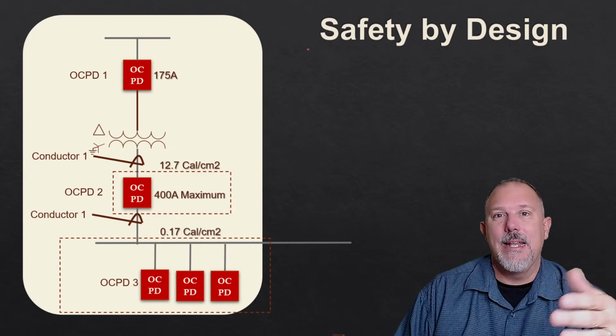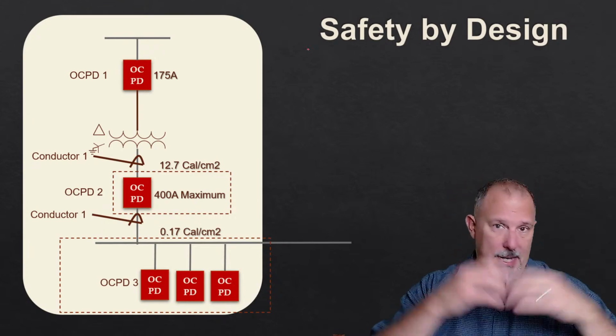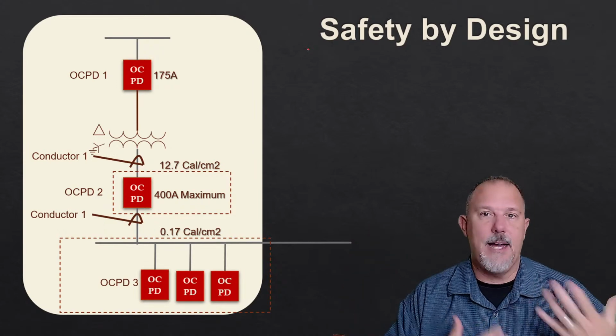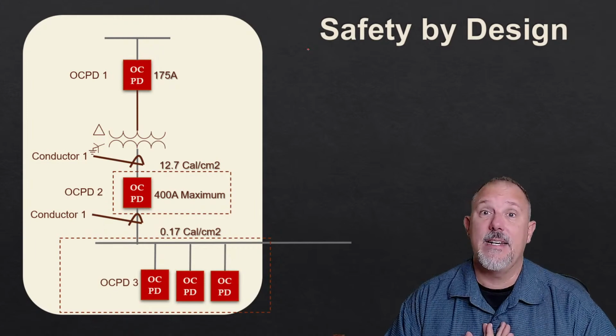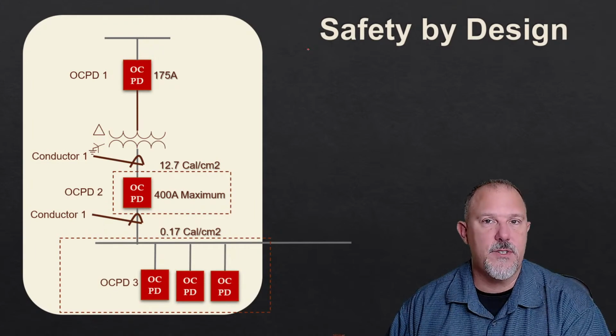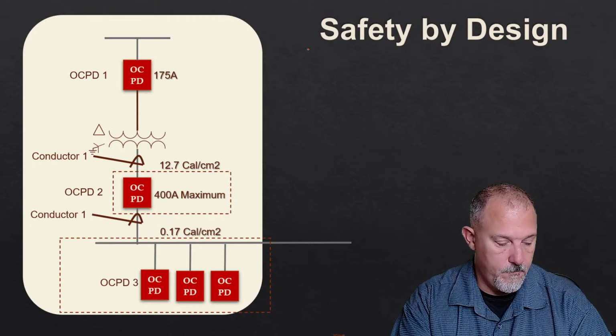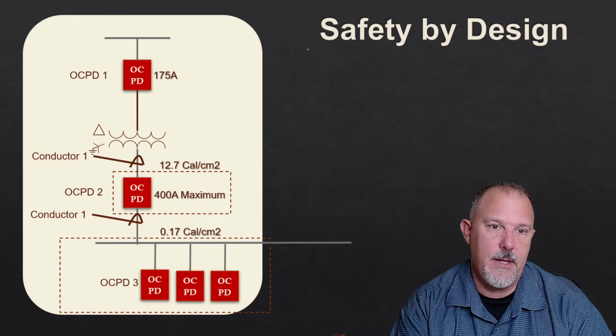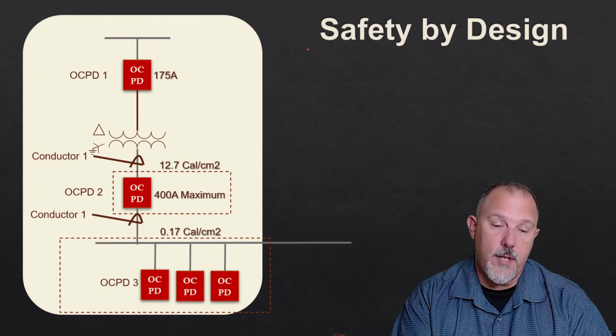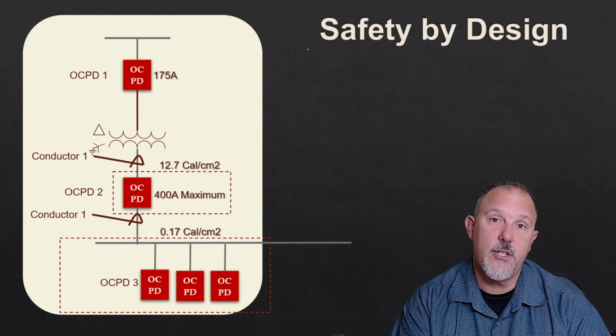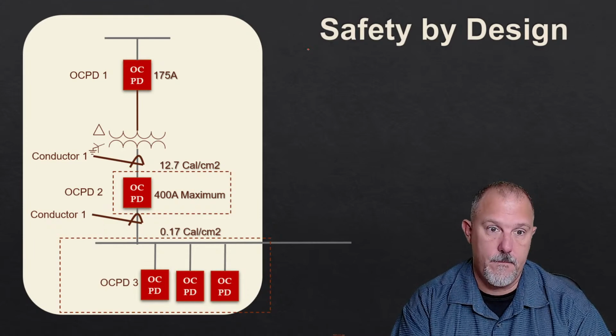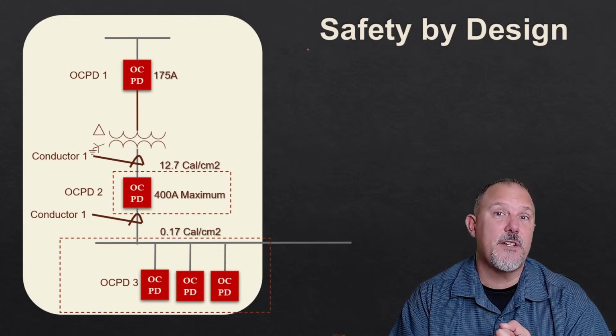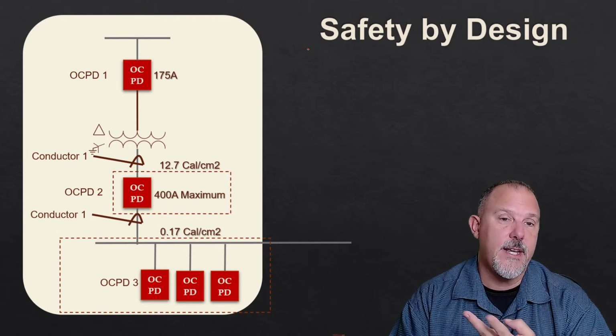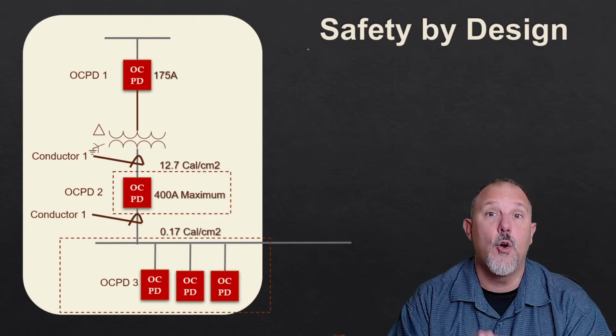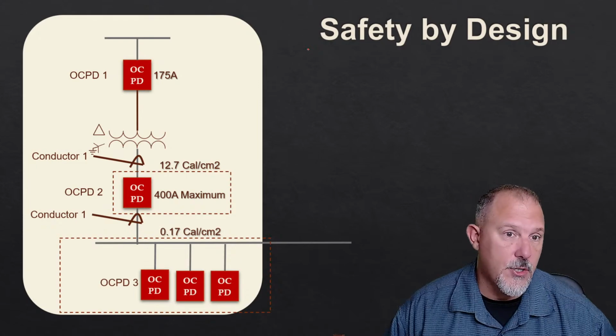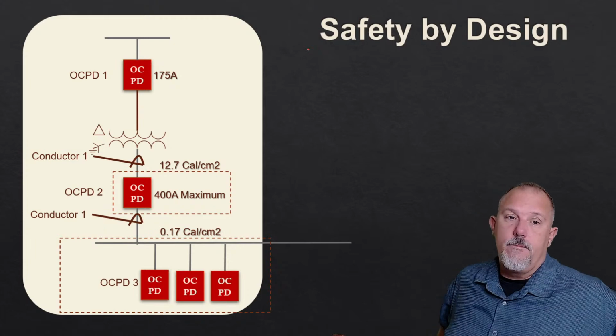But it's not listed to prevent line side propagation. Once that plasma plume goes, there's nothing that says that barrier can prevent line side propagation. My gut tells me it will, but I don't have a third party test to show that. So they said we need to do something about that, and that's where we said, look, the best way to do this is to move that overcurrent device into its own enclosure. And now you can A, facilitate establishing an electrically safe work condition, B, reduce the incident energy, taking it from 12.7 down to 0.17, significantly reducing the hazard for the electrical worker. So it made a lot of sense, and that's how we got there.